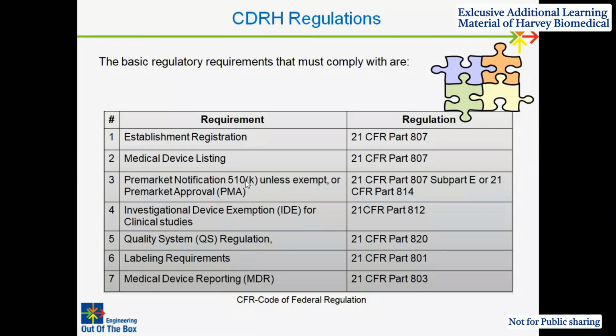Pre-market notification, or 510(k) submission. There is a 510(k) database also as per the US FDA, 21 CFR Part 807 Subpart E. 21 CFR Part 814 is for PMA. This is for pre-market notification, and this is for pre-market approval. There is a slight difference. This is a notification, this is approval. Approval means before I enter the market, we have to take approval. With this we can notify and enter into the market.